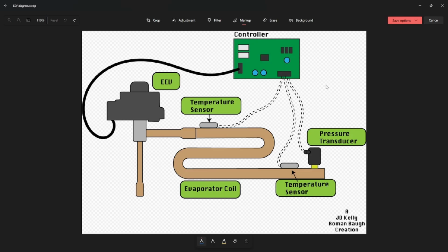They both regulate superheat. That's their main primary function, to regulate superheat at the outlet of the evaporator coil. It's just there to make sure that our coil's doing what it's supposed to and removing the amount of heat it's supposed to. And then they're there to make sure we have enough superheat to keep our compressor protected outside. You would use an EEV over a TXV in high efficiency systems because they're faster to respond. You would also use it in applications where you have an inverter-driven compressor because our compressor modulates and makes changes on the fly very quickly. We need a valve that can keep up with that, and a TXV is just too slow to respond. So it can't keep up with the compressor's modulation. And if we try to run a TXV on an inverter-drive compressor, most of the time it's just going to lead to a dead compressor.